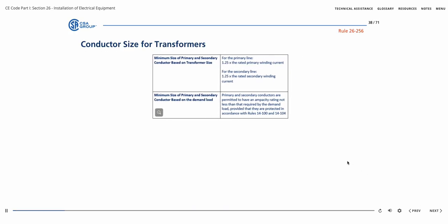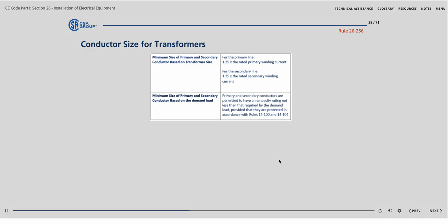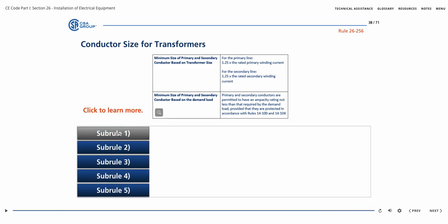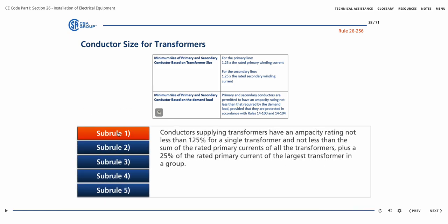It is important to understand conductor size for transformers. Subrules 26-256-1 and 2 explain the requirements. Subrule 1 requires that conductors supplying transformers have an ampacity rating not less than 125% for a single transformer, and not less than the sum of the rated primary currents of all the transformers, plus 25% of the rated primary current of the largest transformer in a group.